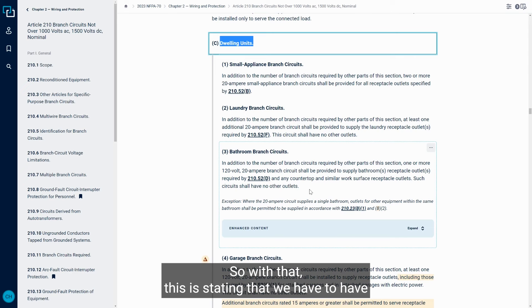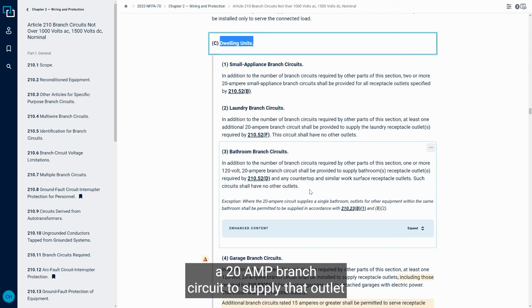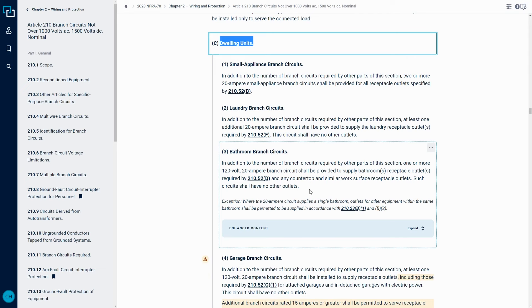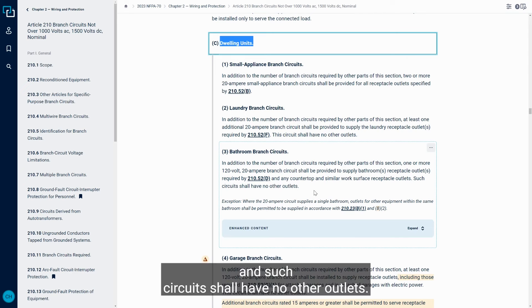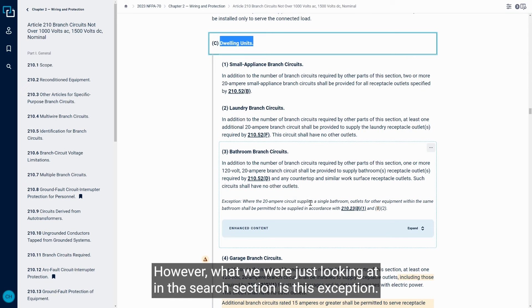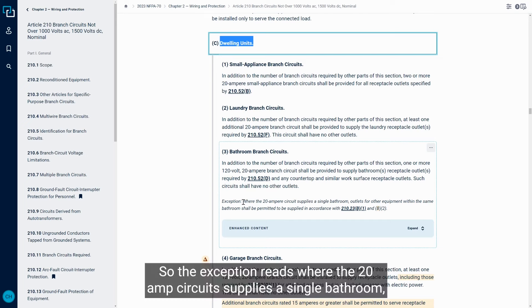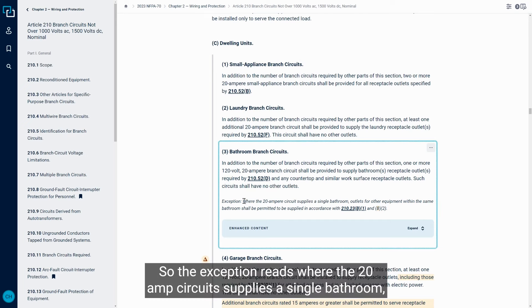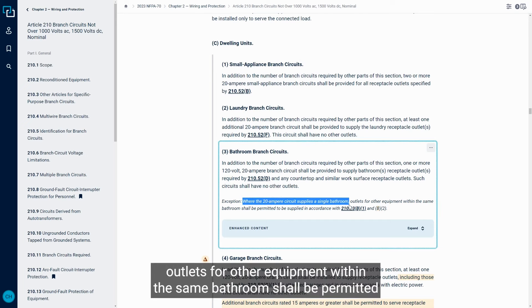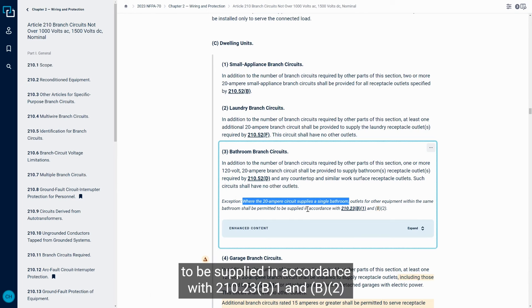So with that, this is stating that we have to have a 20 amp branch circuit to supply that outlet. Okay, such circuits shall have no other outlets. However, what we were just looking at in the search section is this exception. So the exception reads, where the 20 amp circuit supplies a single bathroom, outlets for other equipment within the same bathroom shall be permitted to be supplied in accordance with 210.23.B.1 and B.2.